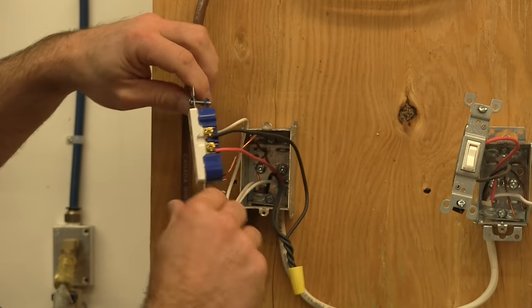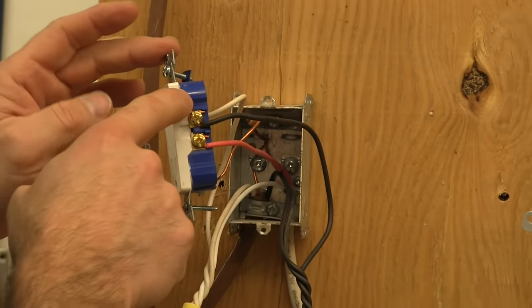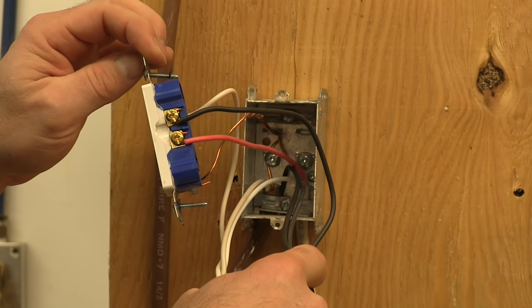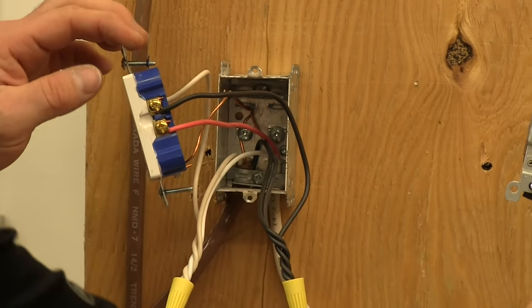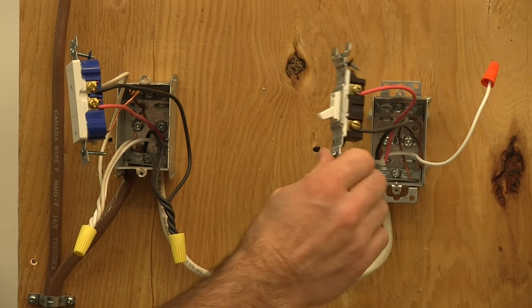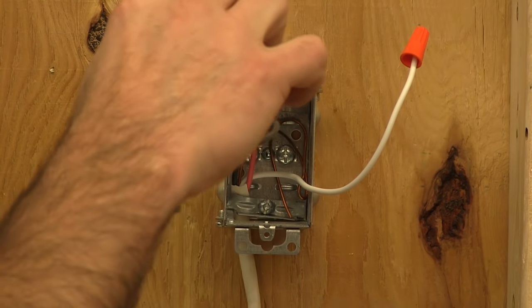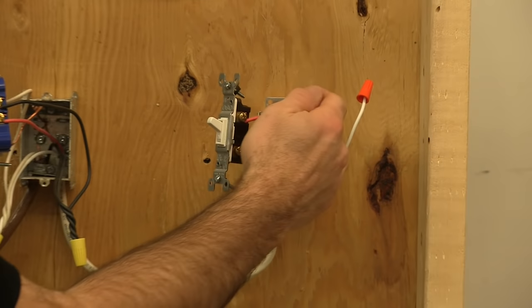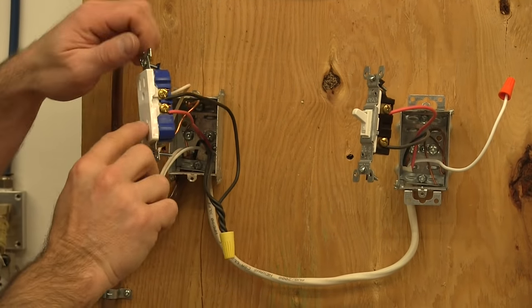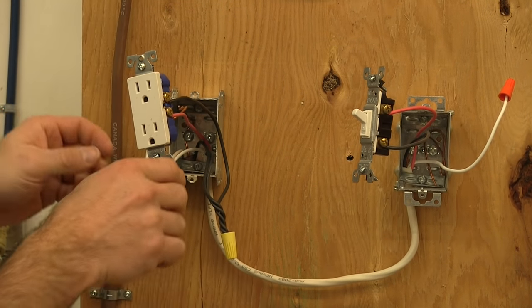Okay, so going back to how the power is running: here's our constant source coming in. This one's always going to be live as long as the breaker's on. Now we have another black wire heading over to our switch in a 14-3 cable that comes to the switch. Here's our black coming in—this is constant power. Then when we flip the switch, it'll travel back through the red all the way back to the receptacle, and that will power up your bottom receptacle. So I think that's pretty clear.